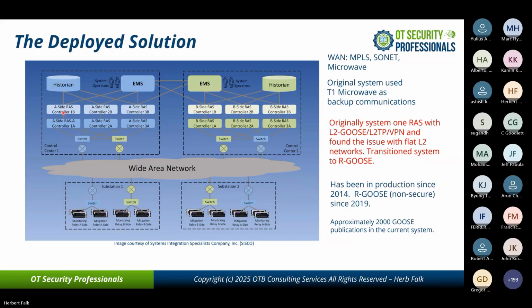So you see a pair of controllers, and 3 pairs in each control center. Now, when you design such a system, where do you put the voting so the IEDs out in the field actually know what action to take? You can't have 2, because if they disagree, there's no way to resolve which one to go with, and you may misoperate. That's why there are 3 pairs here, and the voting was placed in the IED itself. It's a unique architecture from that perspective, because most OT people would say put the voting up here, but that creates a single point of failure.